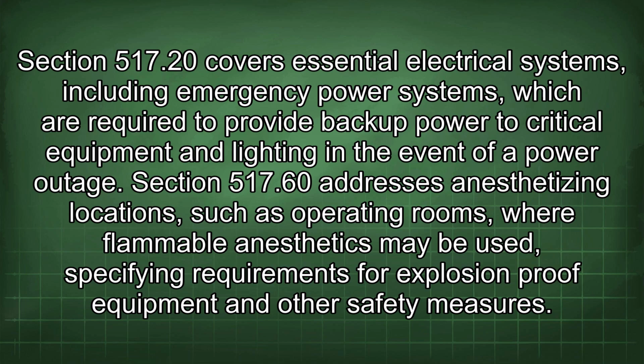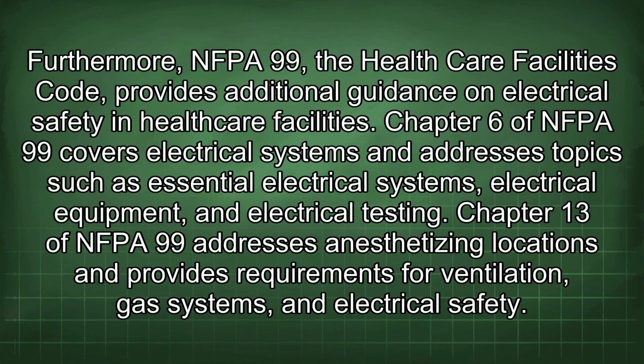Section 517.60 addresses anesthetizing locations, such as operating rooms, where flammable anesthetics may be used, specifying requirements for explosion-proof equipment and other safety measures. Furthermore, NFPA 99, the Healthcare Facilities Code, provides additional guidance on electrical safety in healthcare facilities. Chapter 6 of NFPA 99 covers electrical systems and addresses topics such as essential electrical systems, electrical equipment, and electrical testing.